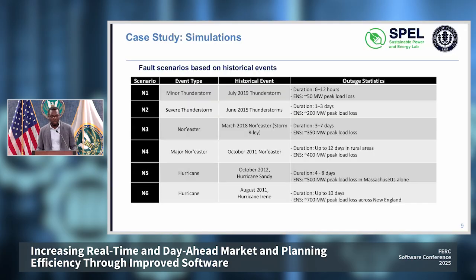For the extreme fault scenario, we based our fault scenario logic on historical events such as minor thunderstorms, severe thunderstorms, nor'easters, major nor'easters, hurricanes, and severe hurricanes, in order of severity from top to bottom. We adapt this logic and introduce scenarios labeled N1 through N6, with N1 being a fault on one line, N2 a fault on two lines, and so on with increasing severity up to N6, a fault on six lines.